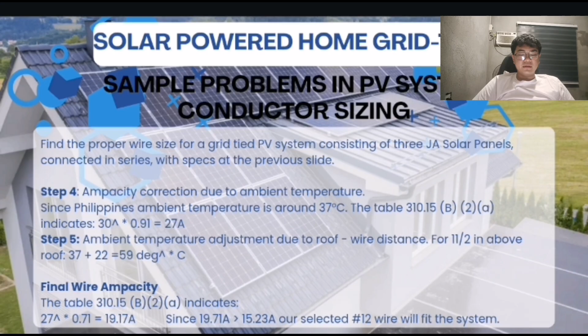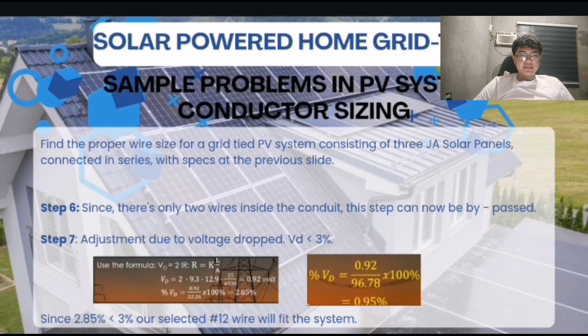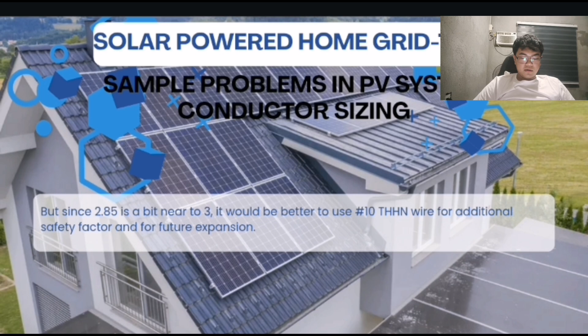So, step 7. Adjustment due to the voltage drop. So, gamit ang formula, masosolve natin dito. So, since 2.85 is less than 3%, our selected wire is number 12. But since 2.85 is a bit near to 3, it would be better to use number 10. Number 10 wire for additional safety factor and for future expansion.